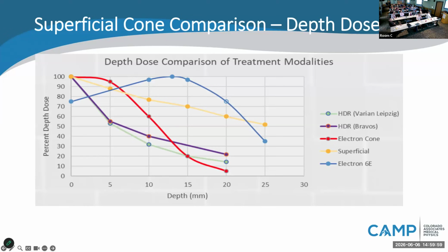So these are some comparisons of our device versus some of the more traditional ones. As you can see in red there, that's our electron cone. If we're treating these squamous and basal cell cancers, which you want to treat down to about a depth of 5 millimeters, we're getting 95% of the dose at that depth. In comparison, for your HDR solutions, you get 100% of the dose at the surface. But if you want to treat with any meaningful depth, you're going to have quite an amount of heterogeneity there. And then for the superficials, that does a better job of treating more uniformly at depth, but there's still a lot of wasted radiation as you get to deeper depths. Whereas since we're dealing with particle therapy, the electron cone really craters after that 5 millimeters, so you're getting very, very little dose at depth.